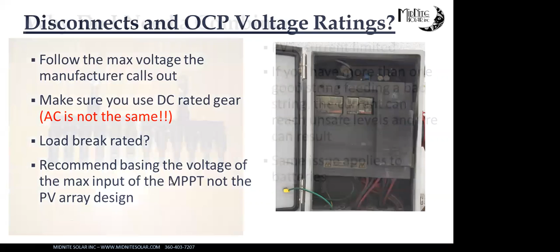So you do have to pay attention to all the markings and labelings and everything like that. A lot of times you might even start seeing 1,500-volt fuse holders. You just definitely need to know the voltage ratings of your equipment so you don't get yourself into some mischief there. Definitely use DC rated gear. Make sure your breakers are load break rated if you're using them with a disconnect. And that should keep you out of most of your mischief there.